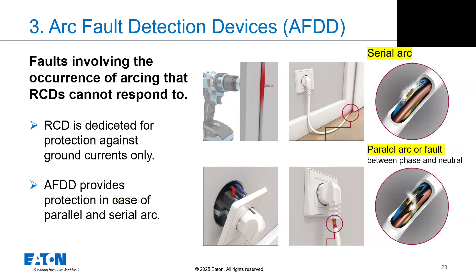But if it is only an arcing situation, it means serial arc or parallel arc, which creates relatively small values of fault currents, for example 100 milliamps or 1 amp, something like this. A normal overload device will not react. Then we must trust the AFDD, and we need to know which protective measure is working or which will not work properly. Some historical overview.